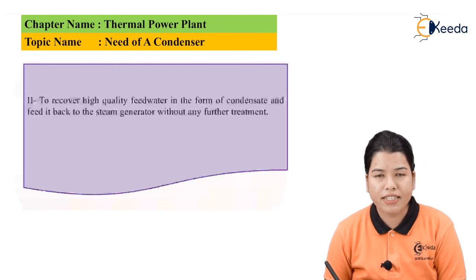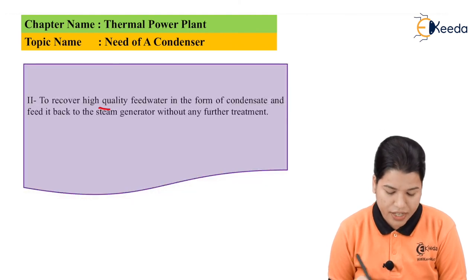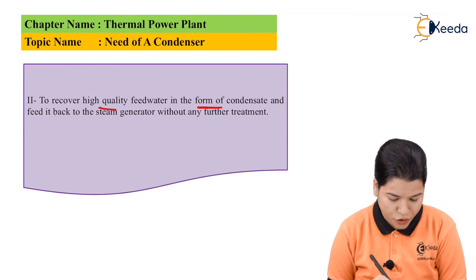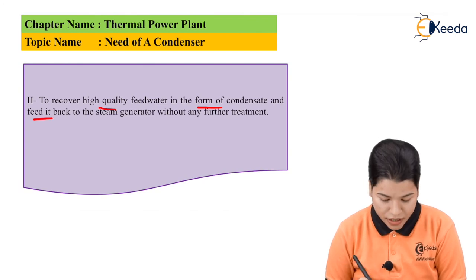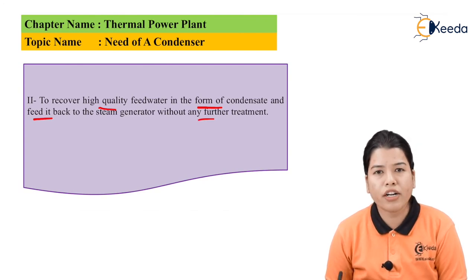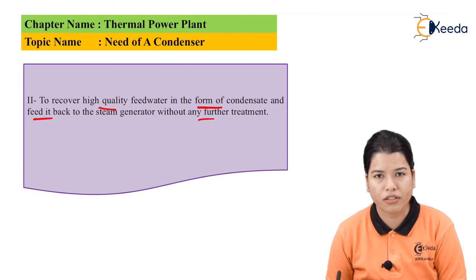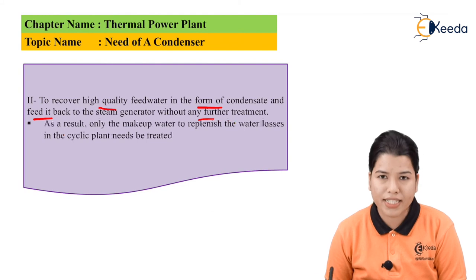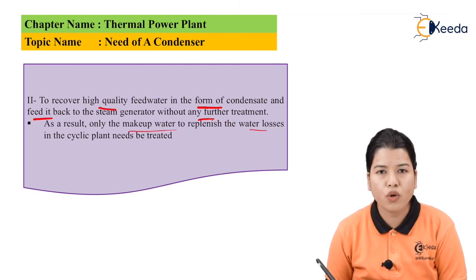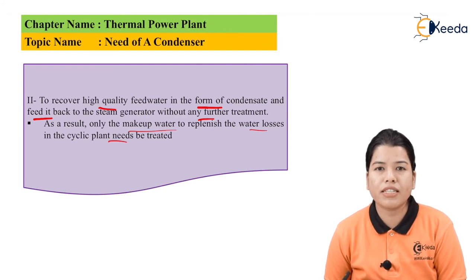The second need for the use of a condenser is to recover high quality feed water in the form of condensate and to feed it back to the steam generator without any further treatment. The feed water can be used again in the form of condensate for heating the water. As a result, only the makeup water to replenish the water losses in the cyclic plant needs to be treated.